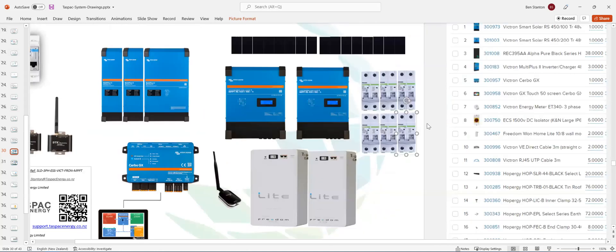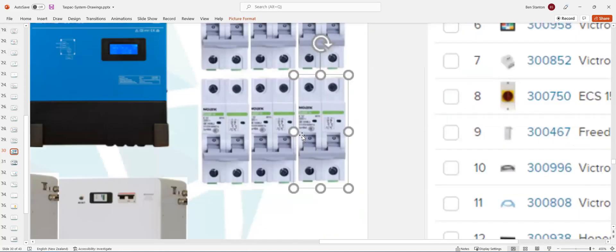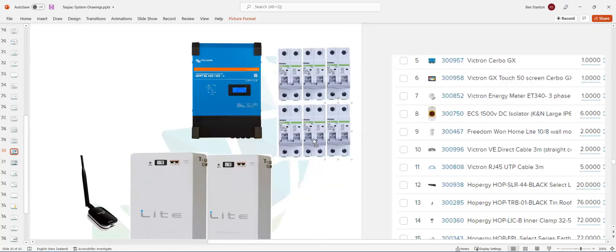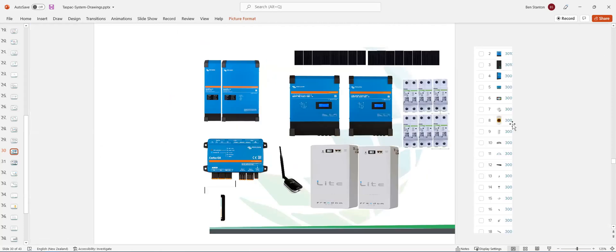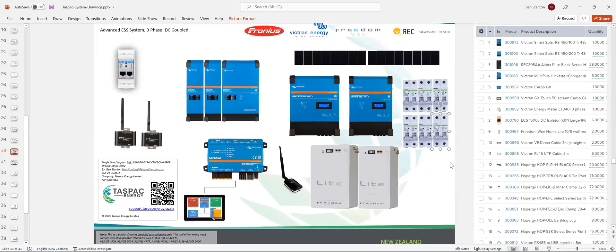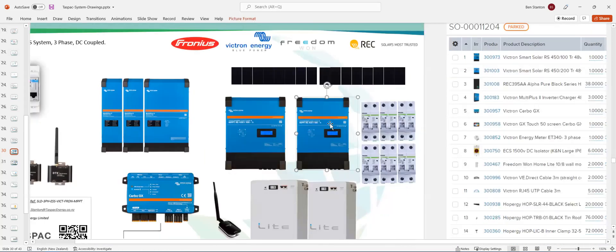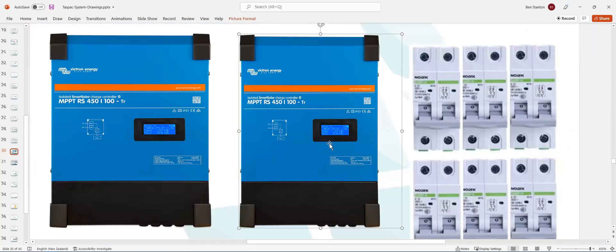You've got six circuit breakers instead of the six DC isolators that were going to be supplied. So six circuit breakers, and they are just fused isolators, effectively. No, not fused. They're just isolators, basically, to isolate the strings coming into the MPPTs.